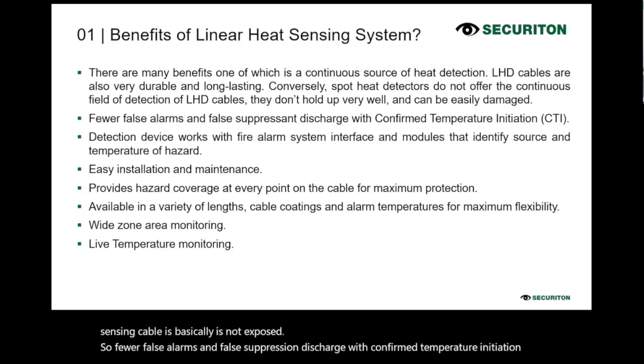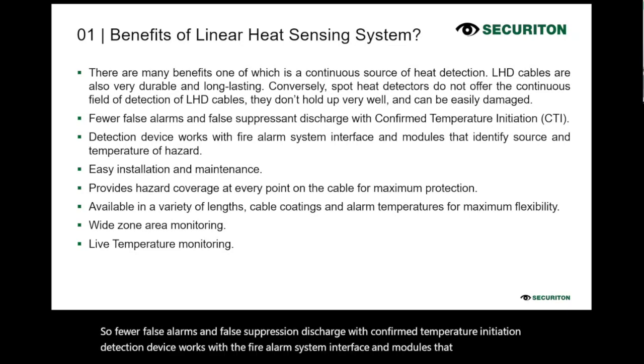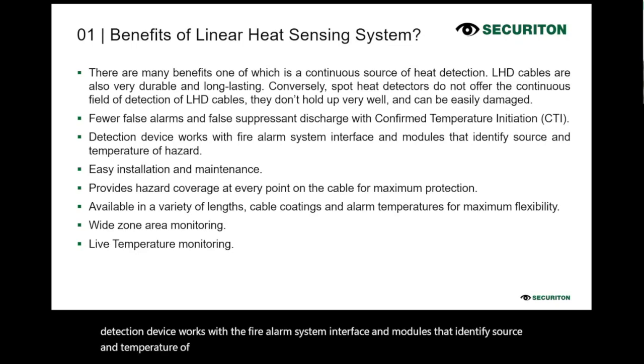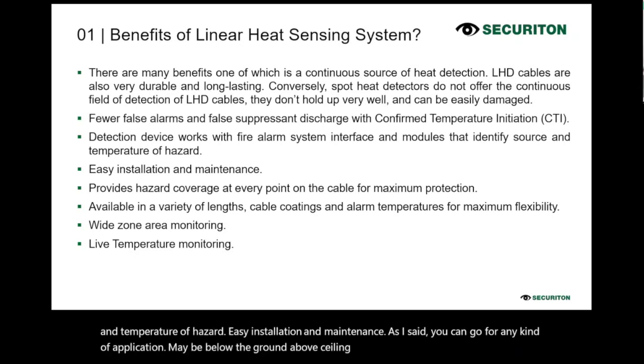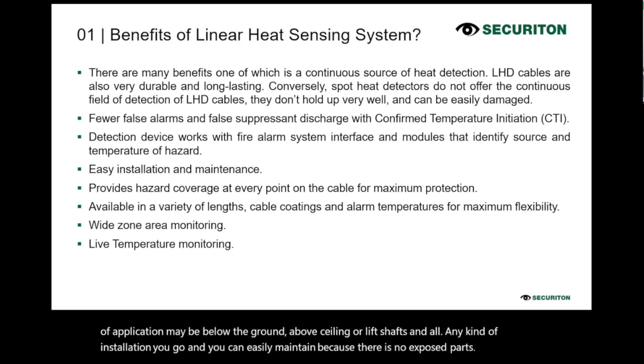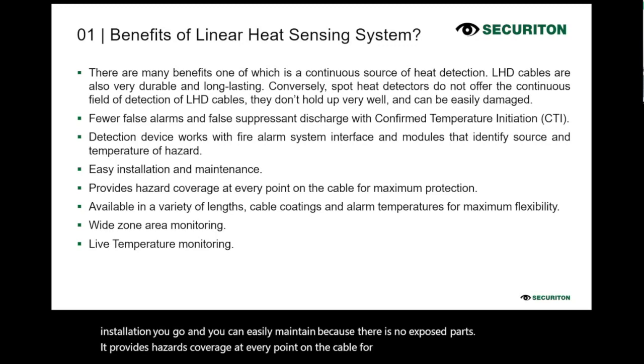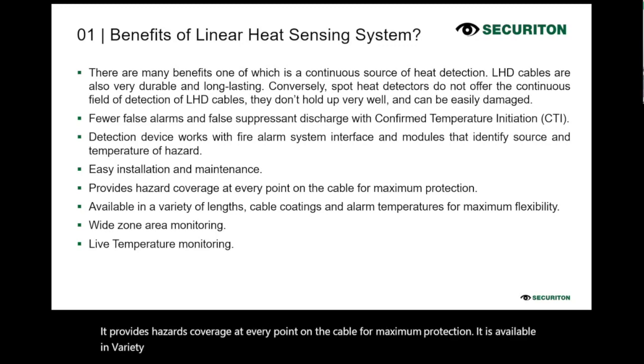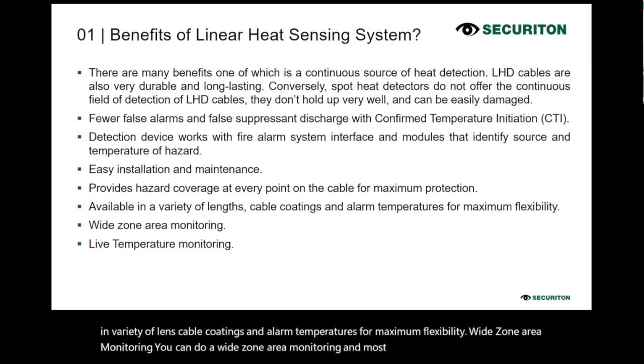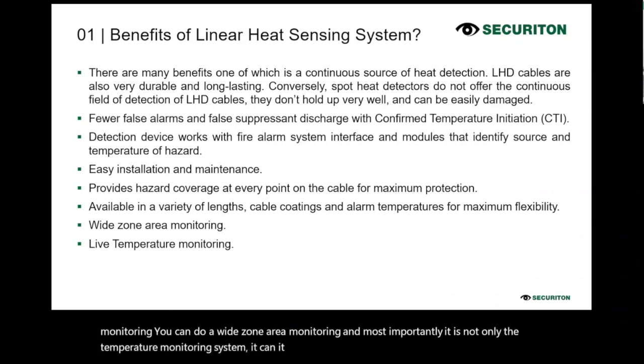The detection device works with the fire alarm system interface and modules that identify the source and temperature of the hazard. Easy installation and maintenance. As I said, you can go for any kind of application, maybe below the ground, above the ceiling, or lift shafts and all. Any kind of installation you go for, you can easily maintain because there are no exposed parts. It provides hazard coverage at every point on the cable for maximum protection. It is available in a variety of lengths, cable coatings, and alarm temperatures for maximum flexibility. You can do wide zone area monitoring, and most importantly, it is not only a temperature detection system, it can monitor live temperature as well. So you can use these cables for detection as well as live temperature monitoring.